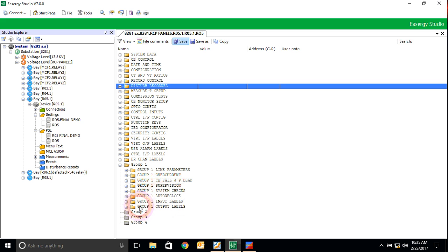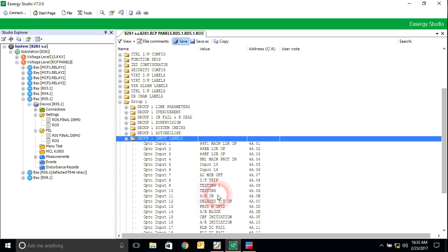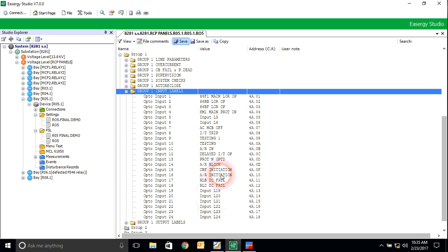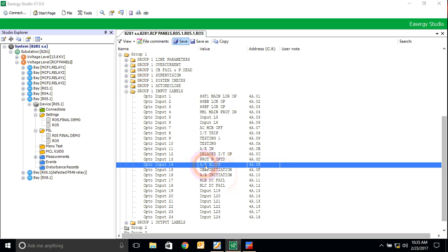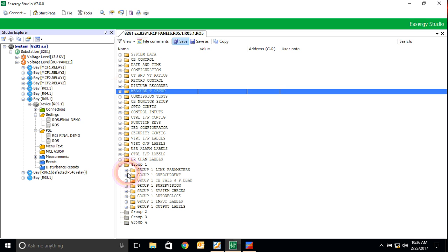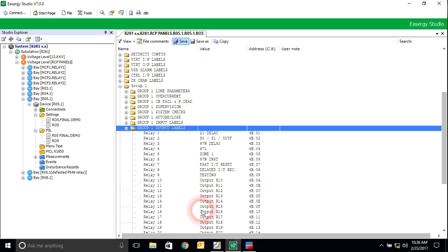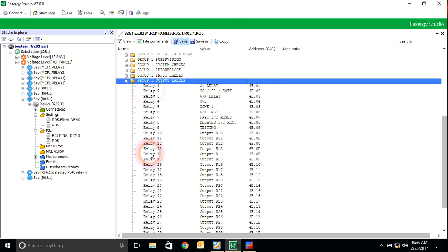After this one, now I am ready to start the autorecloser. I will give a hint or small information. If you give a name to your binary input, you can add it here, not outside. Here you can change any name. Here you can name it, then okay, then after save, go to PSL and extract the names from the setting. Select your setting, you change the names and extract. It will provide your own names so you don't get confused or disrupted in your work.